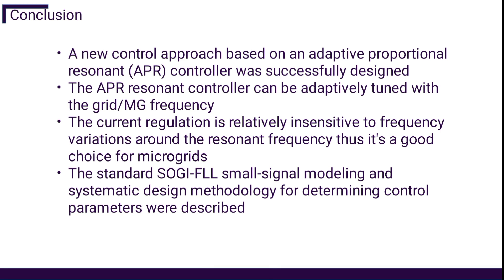In conclusion, a new approach based on an adaptive proportional-resonant controller was successfully designed. The PR resonance controller can be adaptively tuned with the grid or microgrid frequency, and the current regulation is relatively insensitive to frequency variation around the resonance frequency, making it a good choice for microgrids. The standard SOGI-FLL small-signal modeling and systematic design methodology for determining control parameters were also described.